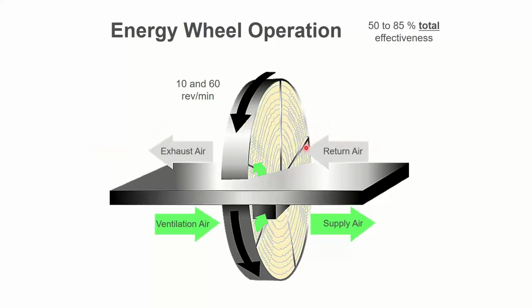There is also some air that could leak down this face of the wheel on the return air that's going to leave. That's called exhaust air transfer ratio. I want to minimize the leakage on the left because I don't want to buy a bigger fan and pay energy to run it. I want to minimize the leakage on the right because whatever's in this return air may not be pleasant, so I don't want it to come back through.